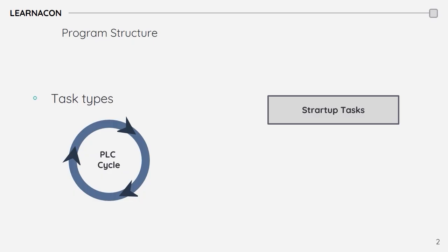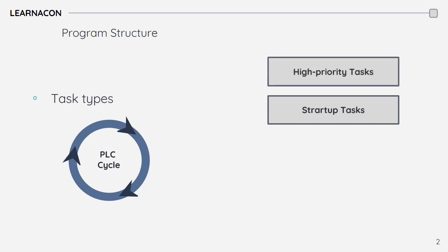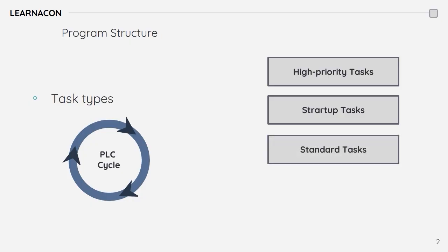Depending on your application, you may have some high priority tasks that if delayed or interrupted by other tasks, the PLC system may fault, stop, or lose the quality. An example would be high-speed motion controls and PIDs. Every PLC offers suitable cycles to program these types of tasks. Most of the tasks fall into a standard category, like sequential logics, interlocks, alarm and error handling, and recipe management.